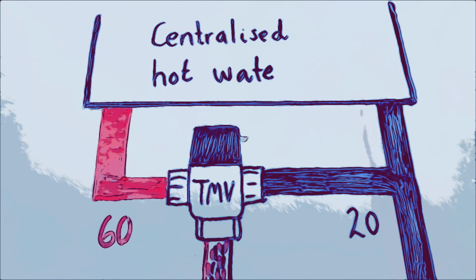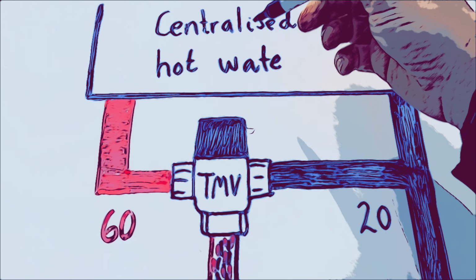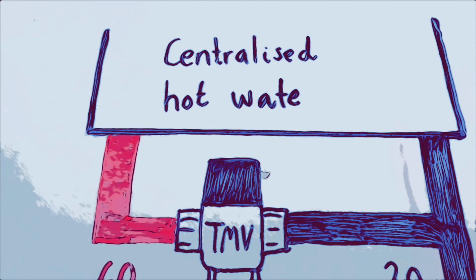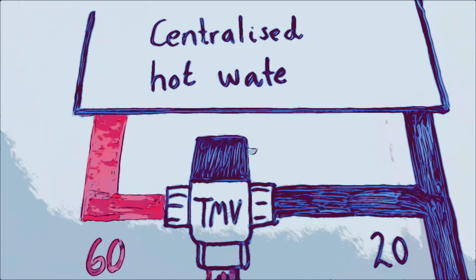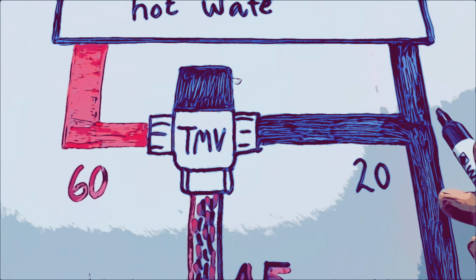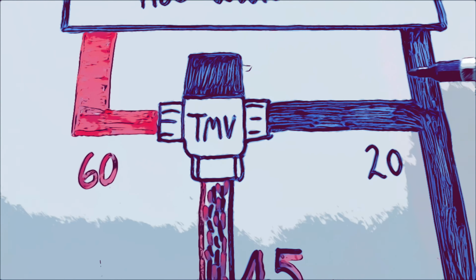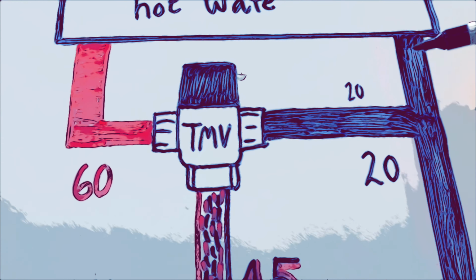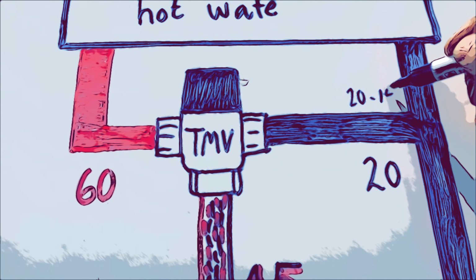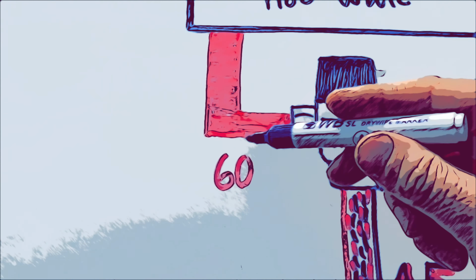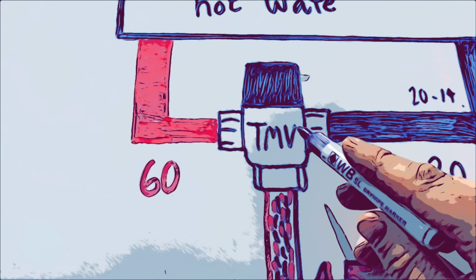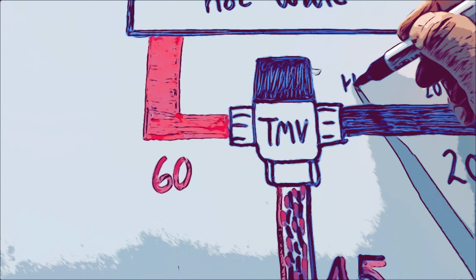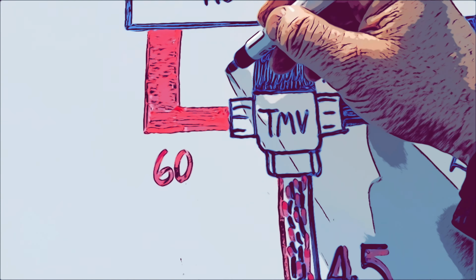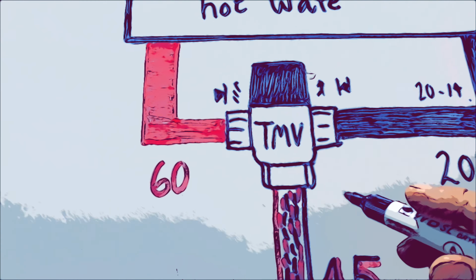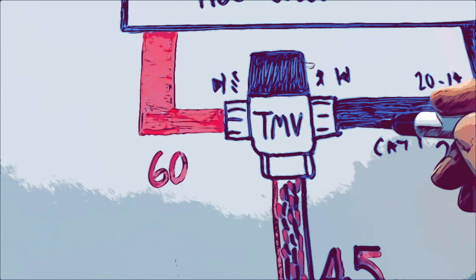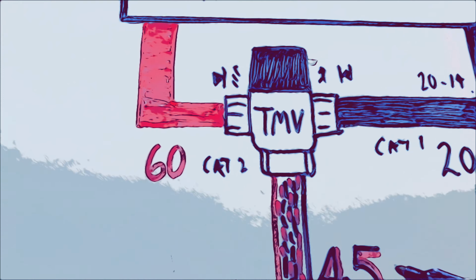How to improve performance of hot water. So here we've got a centralised hot water system. Perhaps it's a combi or a storage combi, or maybe even some form of unvented system. Here we've got a temperature mixing valve, incoming cold supply. So here we've got 20 degrees coming in, and this could be, let's say for example, 20 litres per minute, or perhaps even 14 litres per minute. Temperature 20 degrees, heated temperature here is 60 degrees. So this is a temperature mixing valve. And remember, on the incoming supplies you've got a single check valve, and you've got a filter, single check valve and filter. That's because this is a Cat 1 fluid category, and this is a Cat 2 fluid category, so they don't mix.